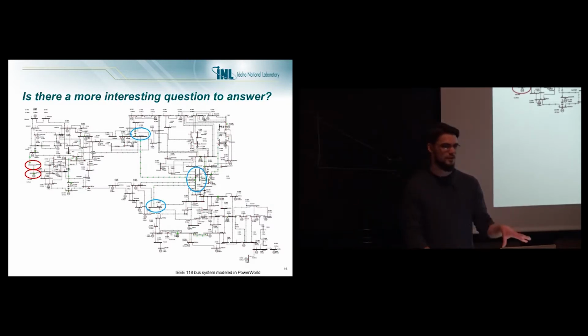So this is the kind of analysis we're working on. Now we know maybe we need to include some kind of adaptive capacity in buses 9 and 10, or maybe we need to reduce or increase the cut set length—so include more parallel components to the cut sets for buses 9 and 10 and these other blue circles. There are many ways we can improve it, but the number one thing is we can just start improving the circuit breakers so they don't fail as often, or improve transformers so they don't fail as often.